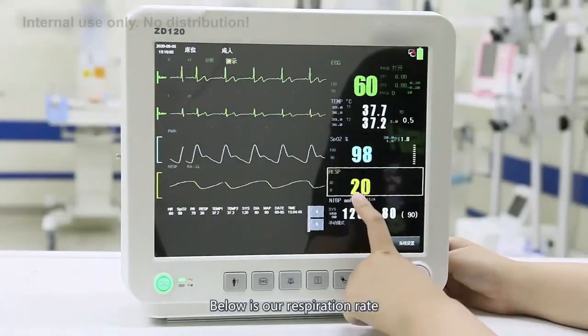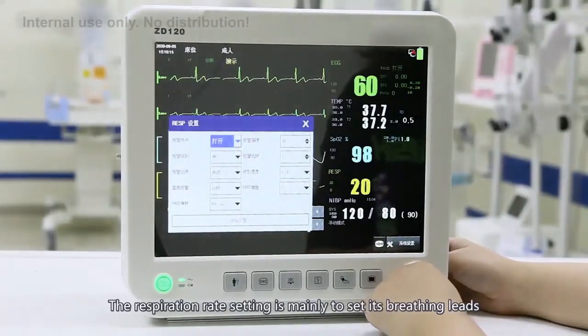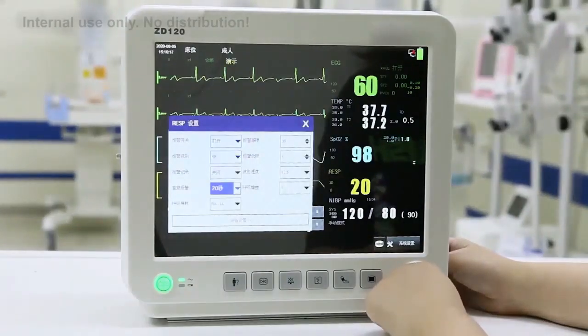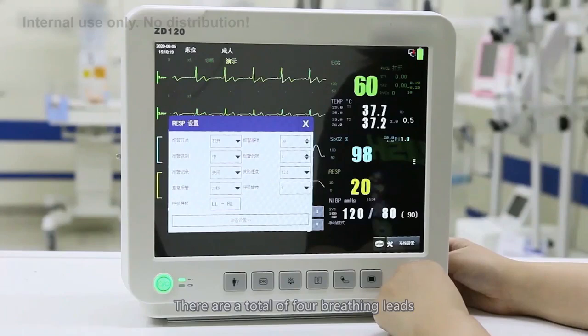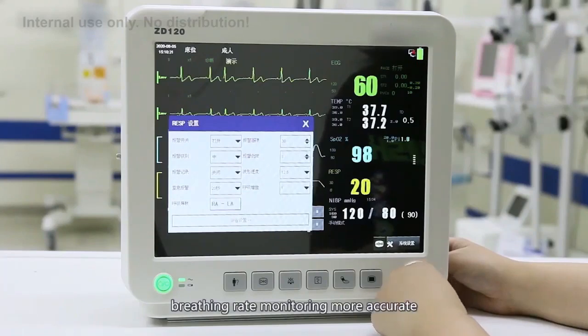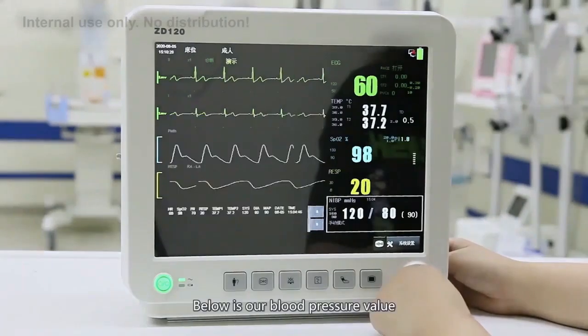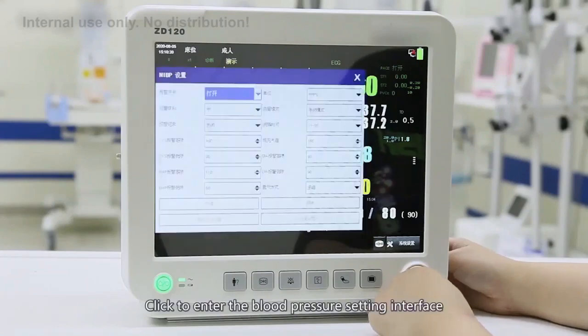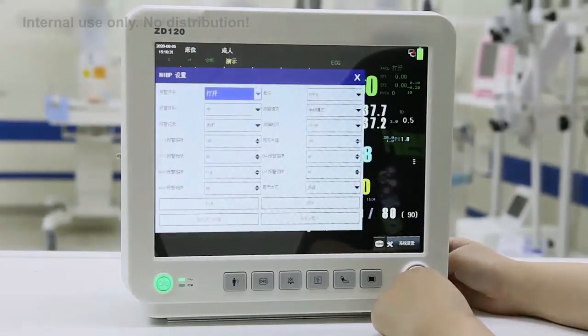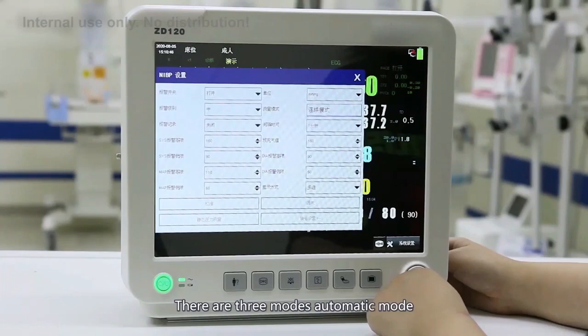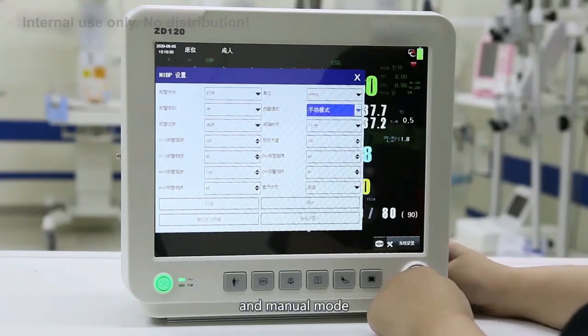Below is our respiration rate. The respiration rate setting is mainly to set its breathing needs. There are a total of 4 breathing needs that can be selected to make breathing rate monitoring more accurate. Below is our blood pressure value. Click to enter the blood pressure setting interface, and you can set the measurement mode.